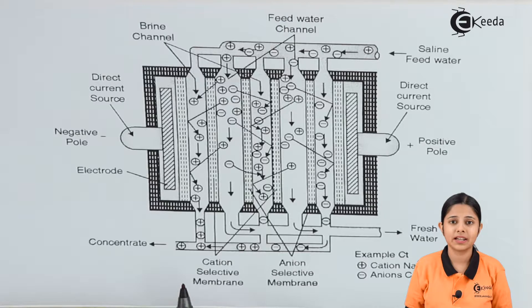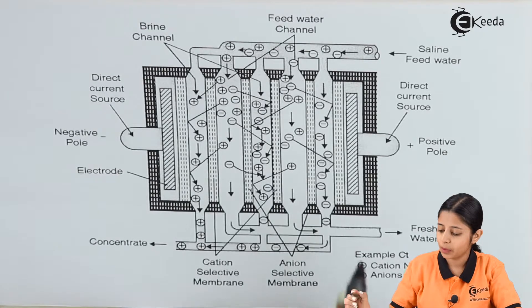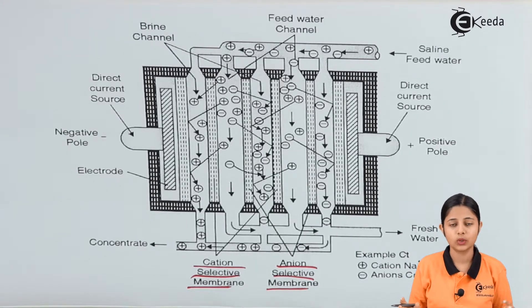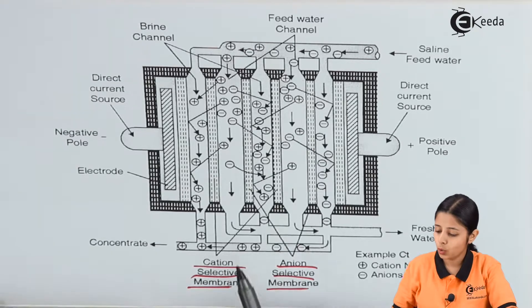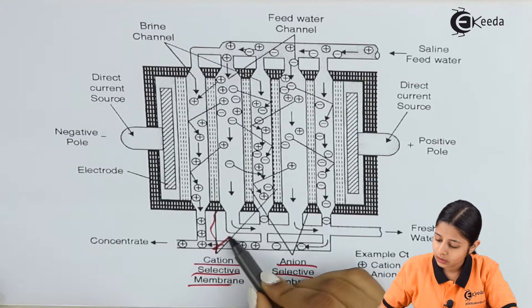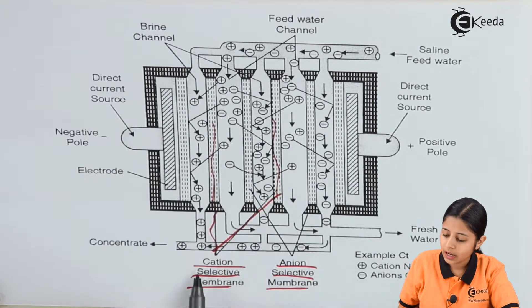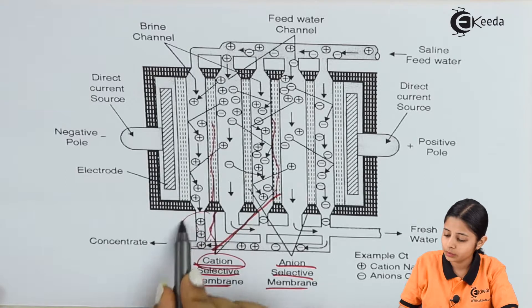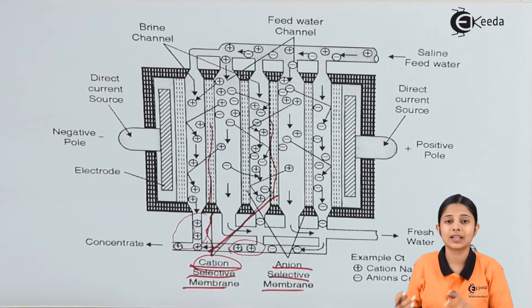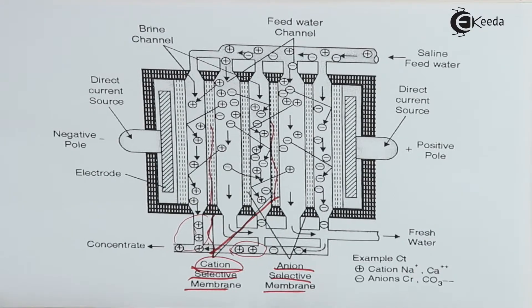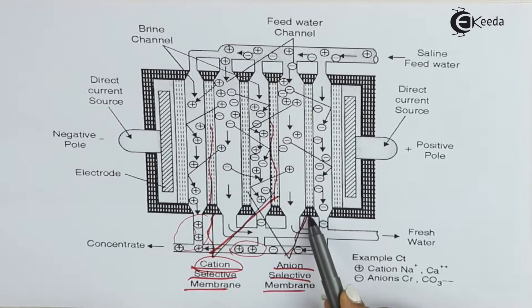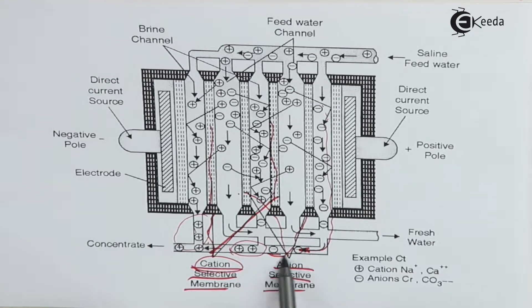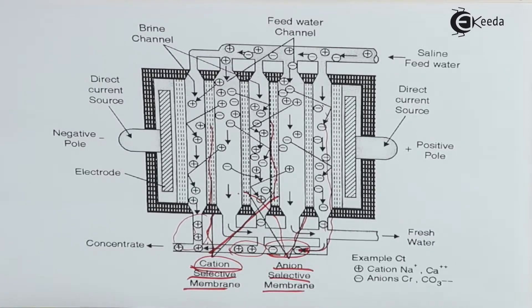Looking at the diagram that explains the entire process of electrodialysis, there are two types of semi-permeable membranes: cation selective membranes and anion selective membranes. The cation selective membranes allow cations to flow through them — you can see positive ions flowing down through these membranes, getting concentrated and eventually removed from the water. The anion selective membranes allow negative ions to flow through them. These anions flow and get collected in the concentrate and are removed. Examples of cations shown are Na+ and Ca2+; examples of anions are Cl- and CO3 2-.